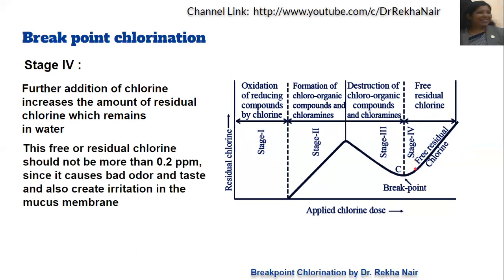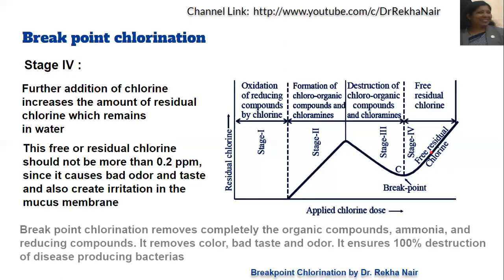This free residual chlorine should not be present in excessive amounts — it should be in the range of about 0.1 to 0.2 ppm only, because more than that causes bad odor and taste and also creates irritation in the mucous membrane. In summary, breakpoint chlorination completely removes organic compounds, ammonia, all reducing compounds, color, bad taste, odor, and all bacteria and germs — giving 100% destruction of all disease-producing bacteria and other compounds.